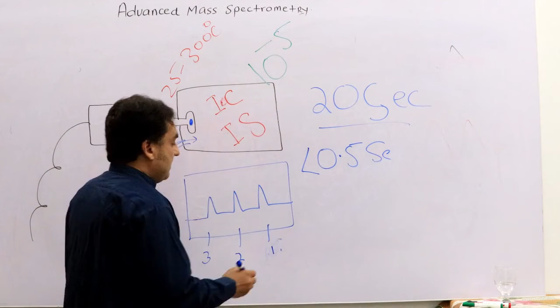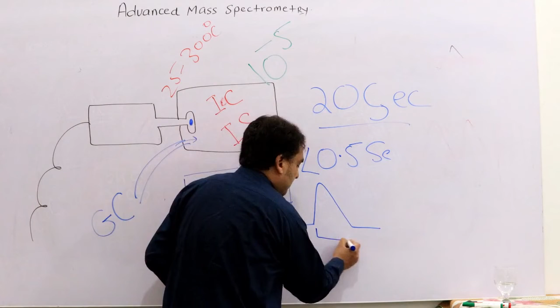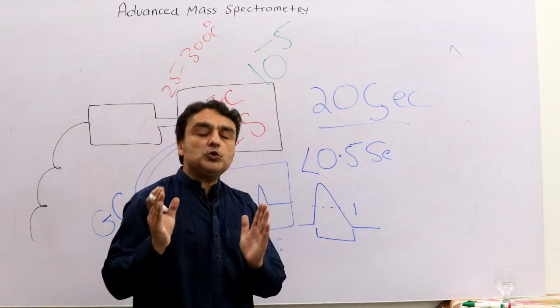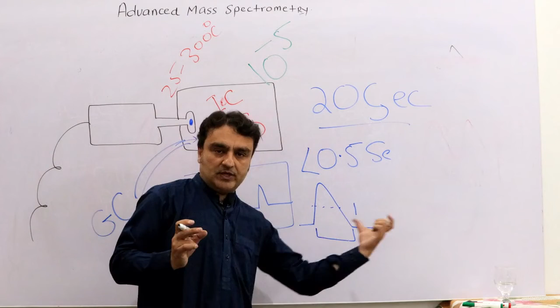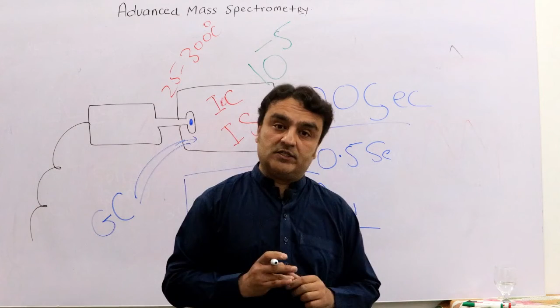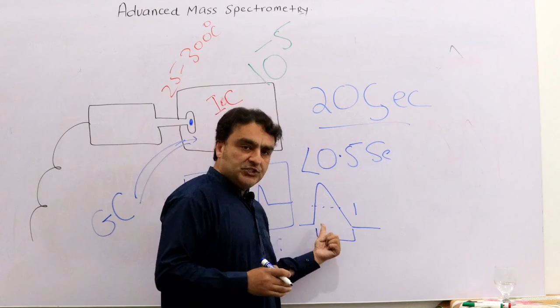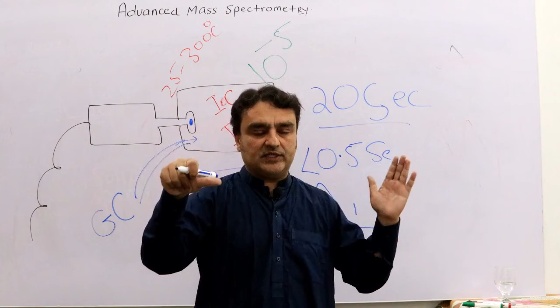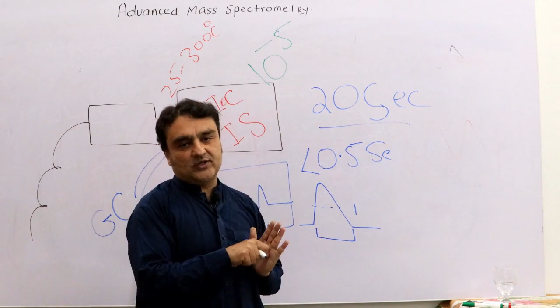Why? Because for each peak coming out of the gas chromatogram, this is not relevant to the mass spectrometry students, but just for information I am adding this. The peak width at half height is called the half height width. The scanning time should be very much less than the peak width. What's the peak width? The peak width means the time in which the whole analyte is coming. Suppose from here to here the peak width is 1 second. So the mass spectrometer should analyze this sample within 1 second. If it is 0.8 second, then 0.6 is very good for the mass spectrometer to analyze it. But if the peak width is 0.3 seconds and your scanning speed is 0.5, then don't try to hyphenate your gas chromatograph, GC, with the electron ionization, because you are not doing a good thing.